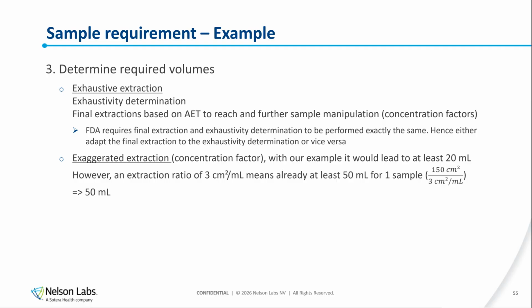But as I said, you need to do this for every single technique that will be used and every single solvent. And then one thing that I want to mention as well for exhaustive extractions is that the FDA requires the final exhaustive extraction and the exhaustivity determination to be performed in exactly the same manner, meaning that the solvent volume, and also the amount of items that you will use and the extraction vessel need to be exactly the same. So you need to adapt the final extraction to the exhaustivity determination, or the other way around, depending on what will be needing the most volume and most items.